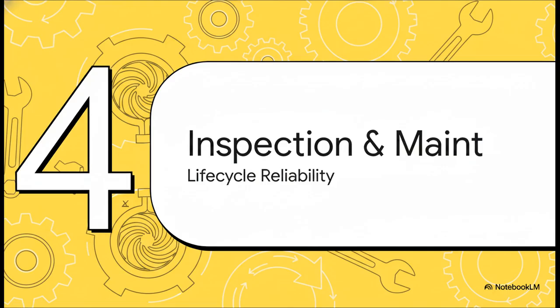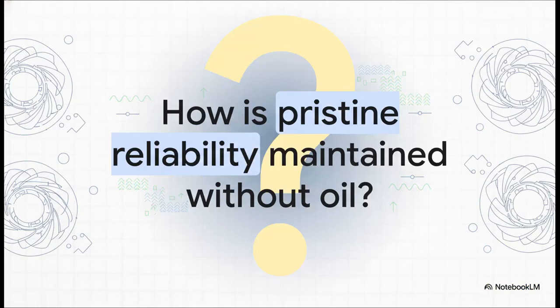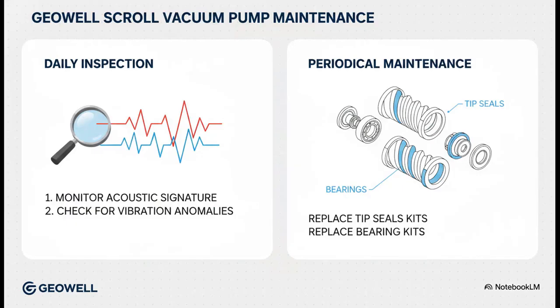Which brings us to Section 4, Inspection and Maintenance, ensuring life cycle reliability. So that raises an obvious question, right? When you're supporting ultra-sensitive manufacturing or high-stakes experiments, how do you actually guarantee this pump holds its rigorous performance standards year after year, especially with zero oil to lubricate it? The answer is a very disciplined, two-tiered maintenance protocol. Tier 1 is your daily inspection. That literally just means paying attention, listening for abnormal noise, feeling for excess vibration, basically just checking the general operational vibe. Tier 2 is periodical maintenance.